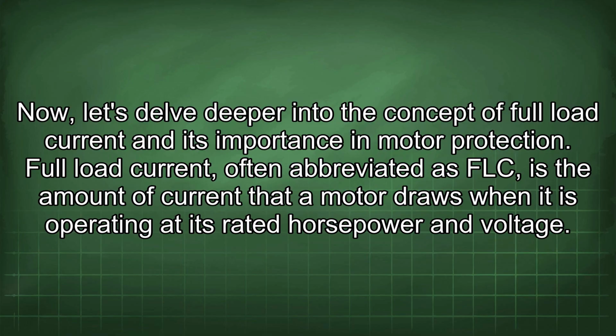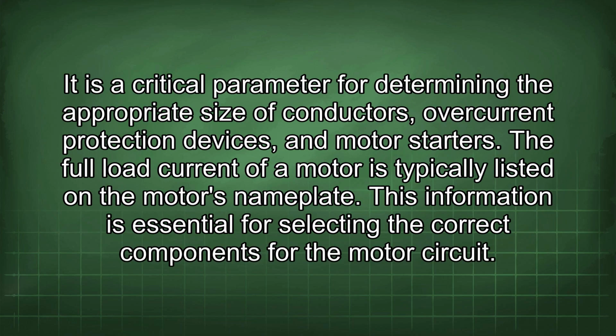Now let's delve deeper into the concept of full load current and its importance in motor protection. Full load current, often abbreviated as FLC, is the amount of current that a motor draws when it is operating at its rated horsepower and voltage. It is a critical parameter for determining the appropriate size of conductors, overcurrent protection devices, and motor starters. The full load current of a motor is typically listed on the motor's nameplate. This information is essential for selecting the correct components for the motor circuit.